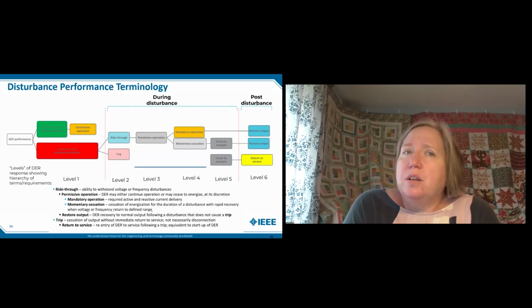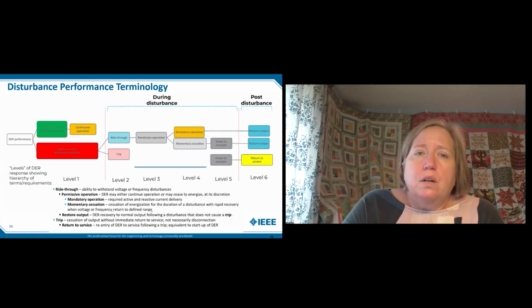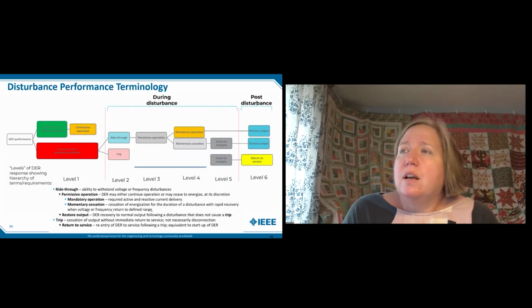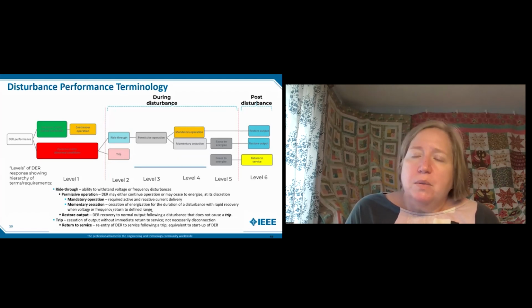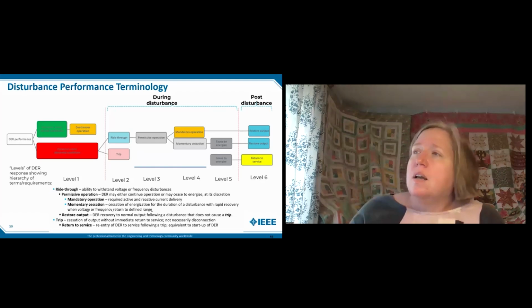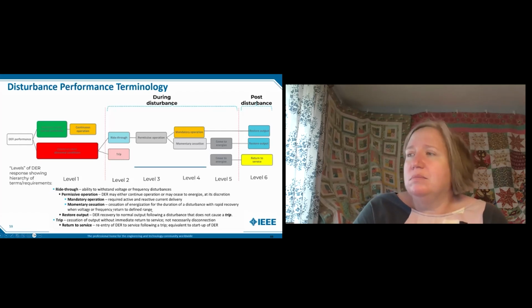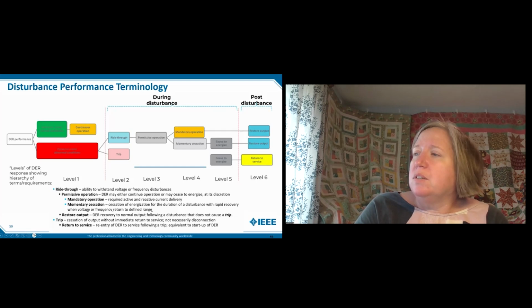So looking at the terminology that we have for the ride-through performance. Ride-through is the ability to withstand the voltage or frequency disturbances. Permissive operation is where the DER can continue to operate, or it can cease to energize at its discretion. You have mandatory operation. You have momentary cessation. Momentary cessation is cessation of injection during the disturbance with rapid recovery when voltage or frequency return to the defined range. So if it's in momentary cessation, it can quickly restore output if it does not go to cease to energize. Restore output is the return to normal.